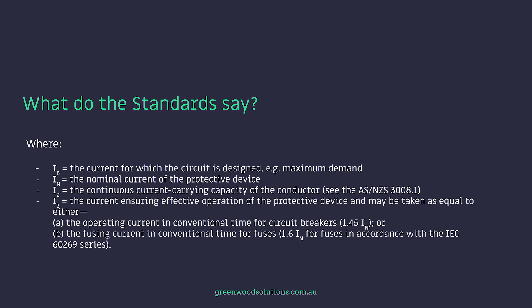I2 equals the current ensuring effective operation of the protective device, and may be taken as either: A — the operating current in conventional time for circuit breakers, which is 1.45 times IN; or B — the fusing current in conventional time for fuses, which is 1.6 times IN, for fuses in accordance with the IEC 60269 series.